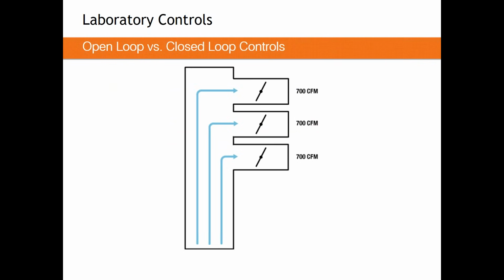Something to consider here is, again, that pressure and airflow are directly linked together. So consider a manifolded system, whether these are fume hoods or operating rooms or whatever it is. Say you have 3 closed loop valves, all flowing 700 CFM through them. If you damper off one of those valves, so imagine closing a fume hood and you close it down to 200 CFM, what's going to instantaneously happen, because the pressure in this system will have risen, is that the airflow in the other valve...